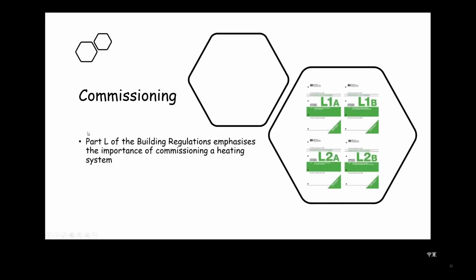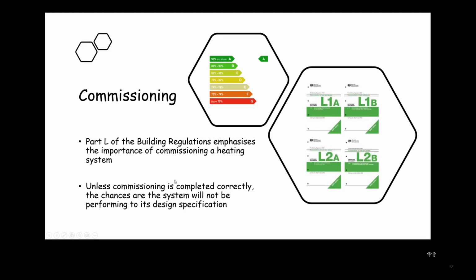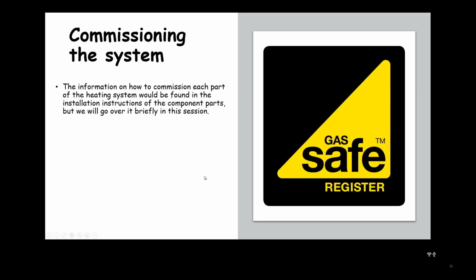So commissioning, Part L of the building regulations puts a big emphasis on the importance of commissioning. The reason for that is if it's completed correctly, the system should work to its design specifications. If it's not completed correctly, it can have a huge impact on efficiency. You'd actually find information on commissioning as part of the installation instructions of each of the component parts, like the boiler, etc. But we're going to go over it briefly in this session.